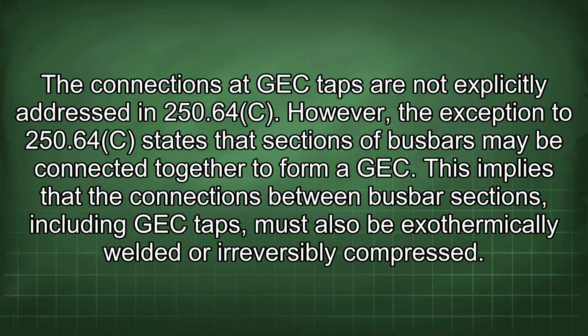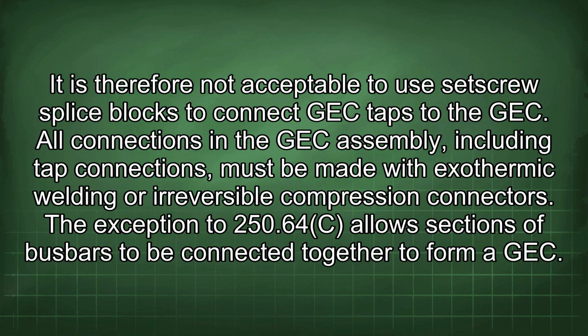250.64(C). However, the exception to 250.64(C) states that sections of busbars may be connected together to form a GEC. This implies that the connections between busbar sections, including GEC taps, must also be exothermically welded or irreversibly compressed. It is therefore not acceptable to use set screw splice blocks to connect GEC taps to the GEC.